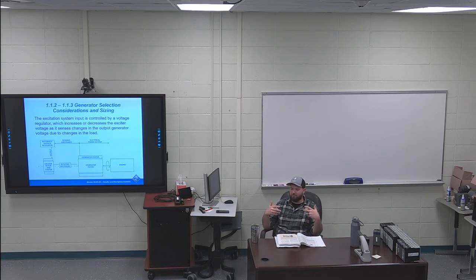So they didn't necessarily have to be oversized, but if you had a building that had to have fire pumps, you might have to oversize it, because those fire pumps are going to take a lot of power to get that water moving and stuff like that. But just know that's one version. Or they've got UPSs, variable frequency drives, battery charging rectifiers. So if you're charging batteries of some type that have to stay on, that are emergency power, those are just different reasons why your generator might need to be oversized.